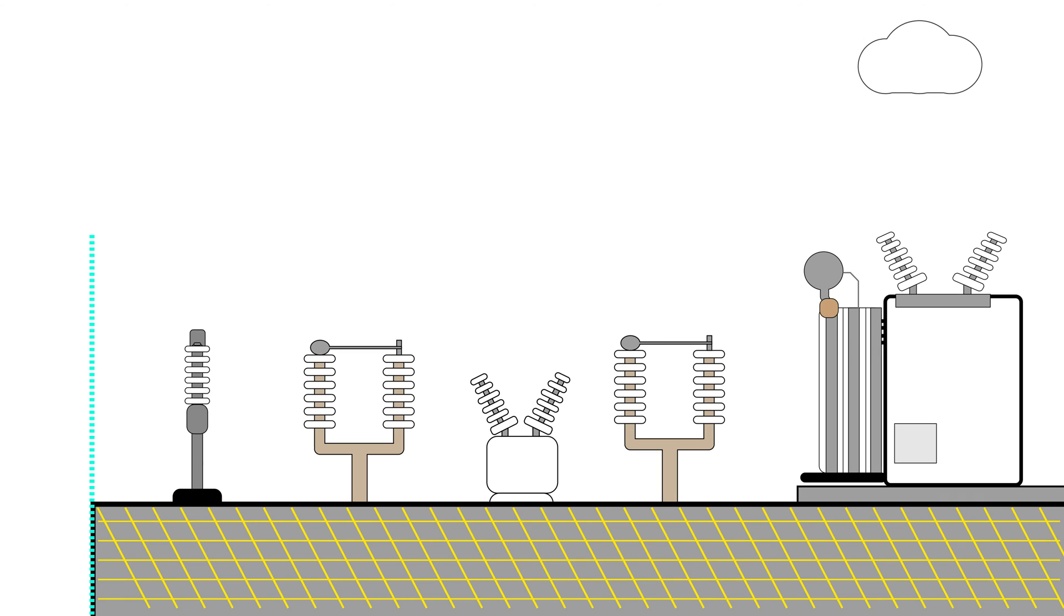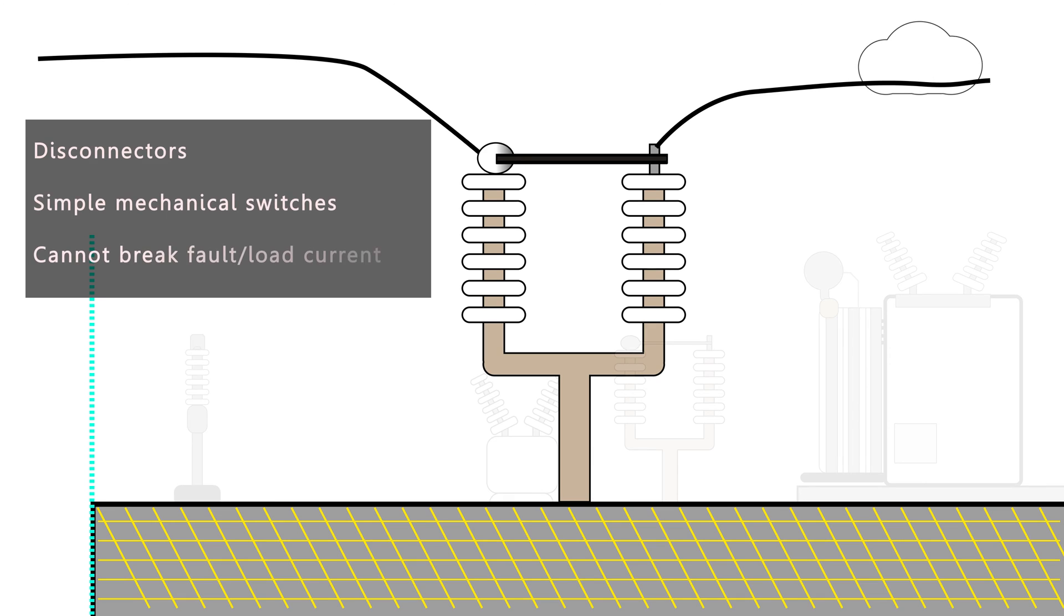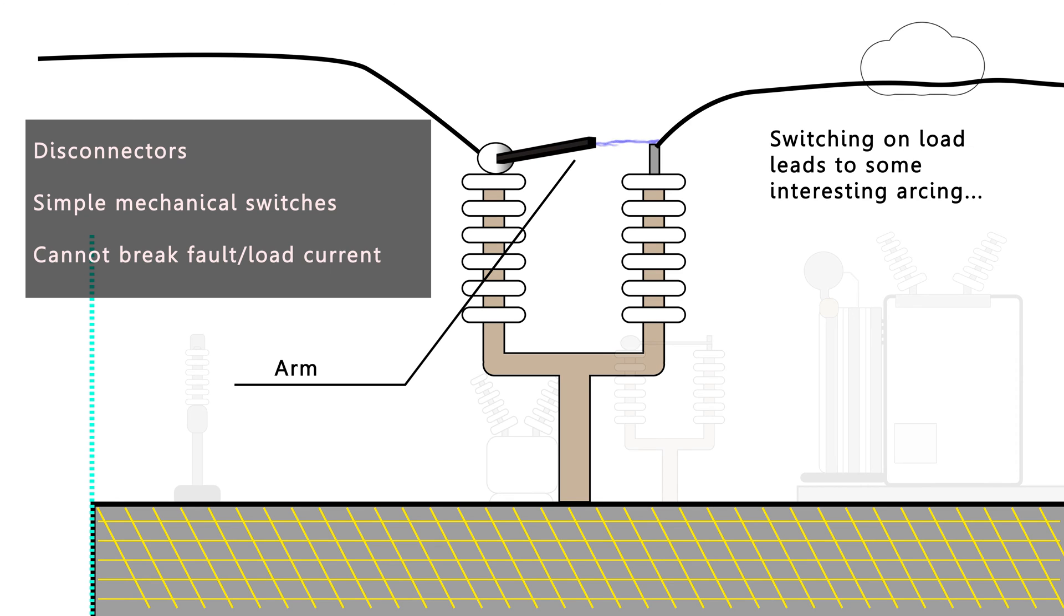The next one we'll look at is called the disconnector. The disconnector is a very simple asset in construction. It's made up of a swinging arm, so this is just really a mechanical switch. Now disconnectors are cheap, they are reliable, but they're not able to break load current or fault current. So that's one of the big weaknesses of a disconnector. In fact, if you try to break load current or fault current, you just get a giant arc. So it's a very specialist job to break fault current and load current.